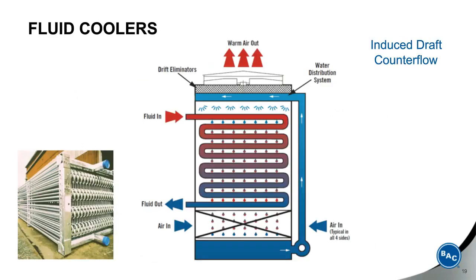Now let's look at various types of closed circuit cooling towers. Here is shown an induced draft counterflow tower, where the hot fluid enters the top of the coil, traverses through a serpentine tube bundle, and leaves cooled out of the bottom. The water in the sump, which is shown in blue, is pumped up over the coil. Air is induced through the fan at the top of the unit, and the evaporative heat transfer occurs inside that tube bundle array, where it basically cools what's inside the tube.